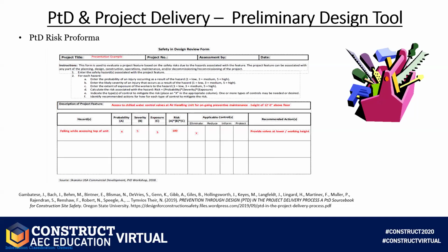So it came out to about a 100 on the scale of 125. The HS&E team decided to eliminate that possibility of somebody having to get up there and possibly being impacted. So what was redesigned was the location of the valves, the piping was reconfigured, and the chilled water control system was basically designed to be at working height right off the floor level. Nobody needed to get up on a ladder or in a lift or climb up in the ceiling around the steel to get to anything. This was all going to be at working height right in front of the face of the individual.